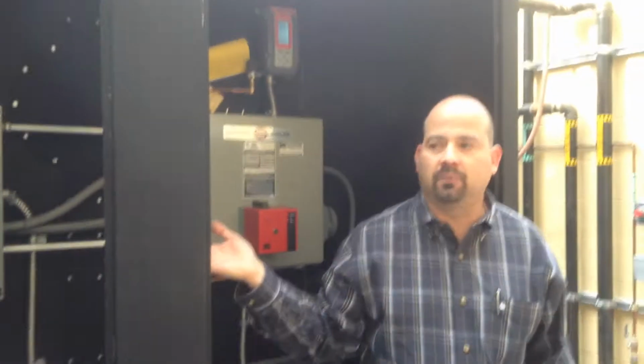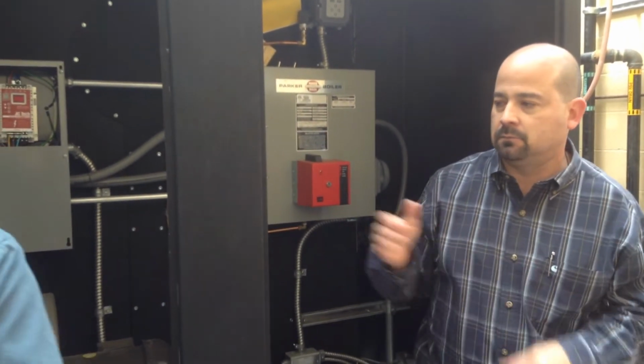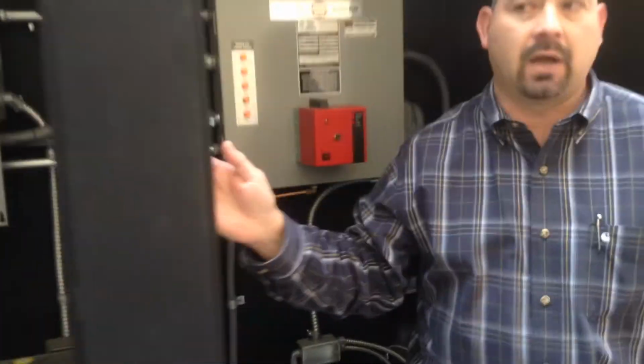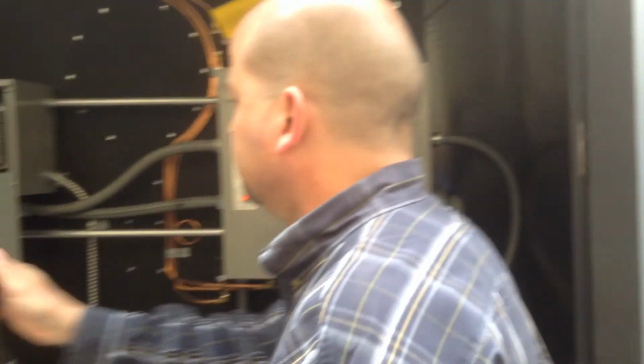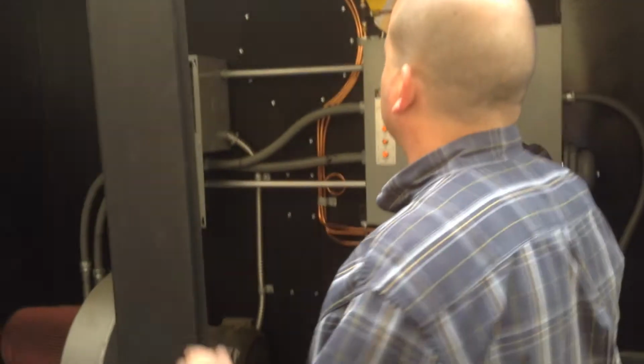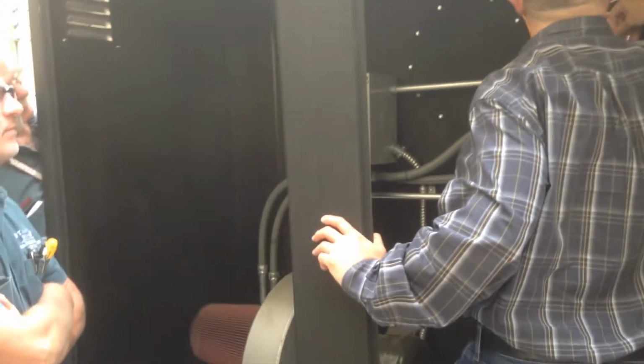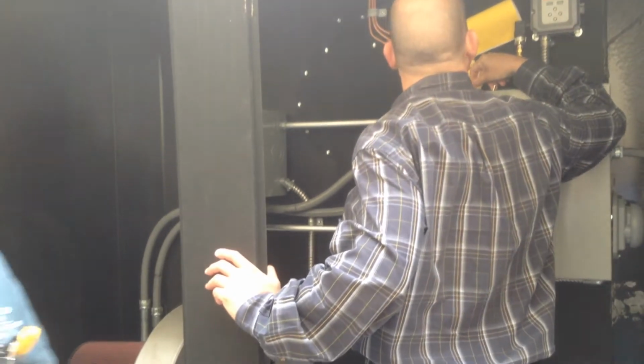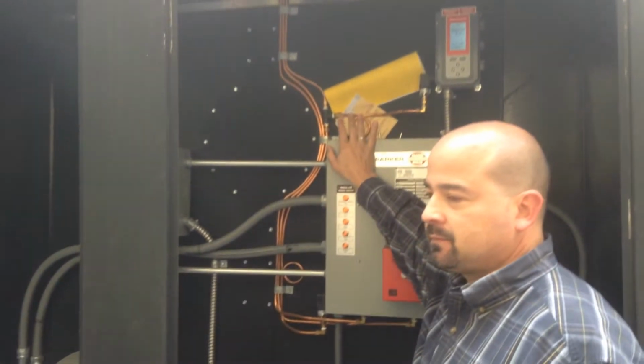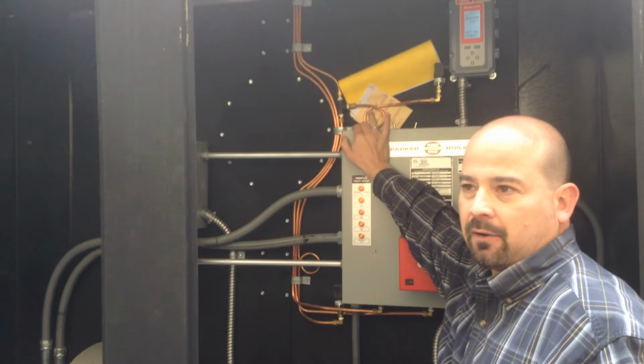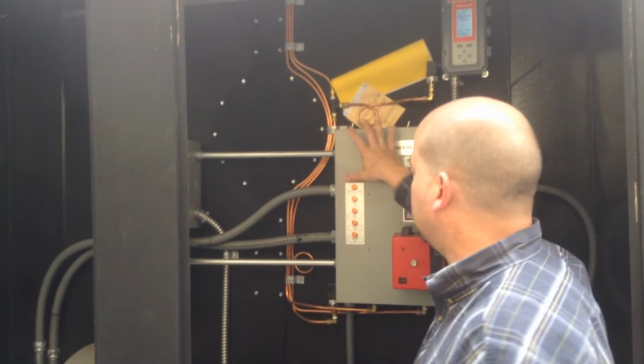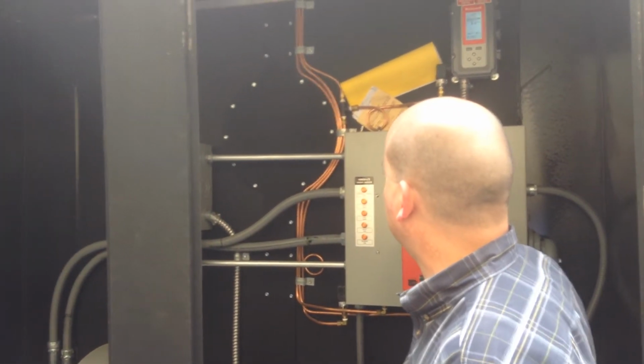So this boiler is a low NOx boiler, which is required by the Air Quality Management District now. All boilers need to be low NOx. So I'm going to go ahead and turn it off for a minute. You have a series of switches on the top. The one on the far left is control power. So that's the 120 volt power that powers this control panel.